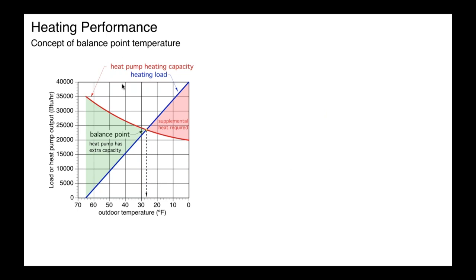Now, another concept with air source heat pumps, and this applies to air to water as well as air to air type heat pumps, is called balance point. And it's a simple idea. If you look at the blue line here, this represents a simple linear model for heat loss from a building. When it's 65 degrees outside, the assumption in this graph is that the building needs no heat input from its heating system. Internal heat gains are sufficient to keep the building comfortable. And as it gets colder, you can see that heat load increases.